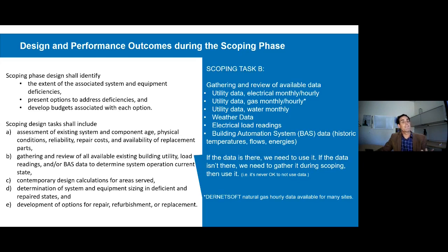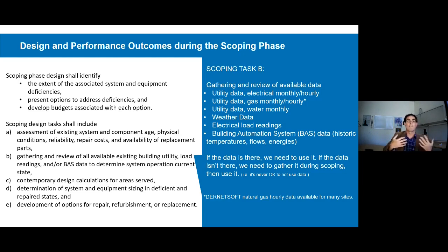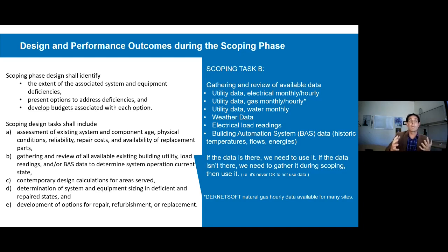Task B is to gather available data and then use it for assessments. We always have utility data available: monthly electrical, natural gas, water use, cost, and weather metrics like cooling degree days or heating degree days. At a very minimum we can calibrate our design ideas to that historical utility data to make sure we're in the right ballpark.